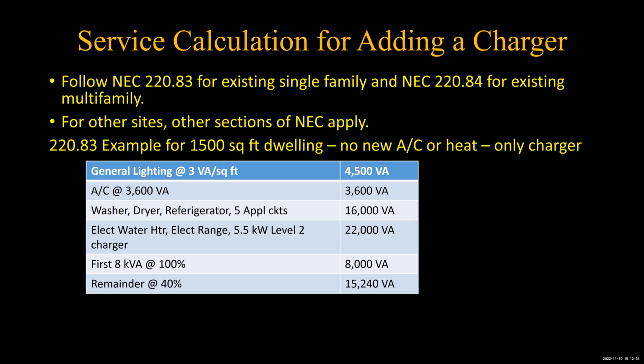You have all these things: the 5.5 kW level 2 charger we want to add, plus the electric range, plus the electric water heater, adds up to 22,000 volt amperes. Then the washer, dryer, refrigerator, and 5 appliance circuits. Normally you'd list them individually, but my screen isn't tall enough for that, so I have to do it this way. So you take your first 8 kVA, not the first 10, but the first 8, because this is an addition, not new construction.